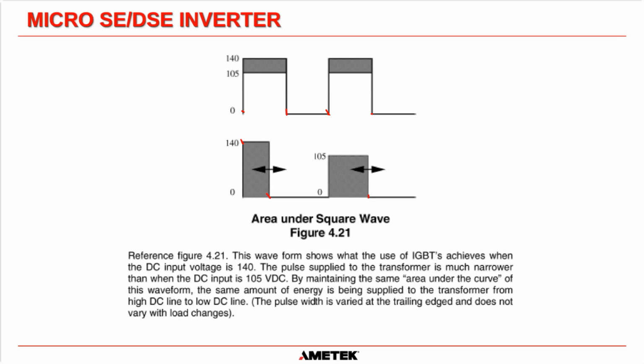Looking at the top, we're saying that between 140 and 105, the area under the curve changes. At 140, we have this additional area here. Remember, you can put your batteries on equalize for a 60 cell system. That will take it up to 140 volts, so we have to allow for that. Your batteries can also discharge all the way down to 105 volts, which is this point here. So the area under the curve changes if we don't control the trailing edge of the signal.